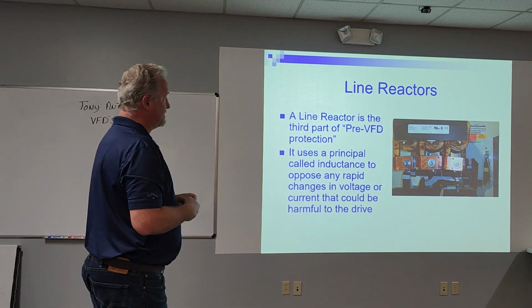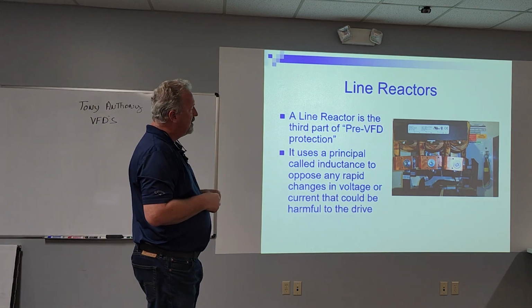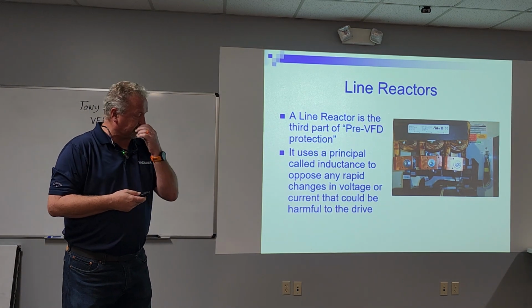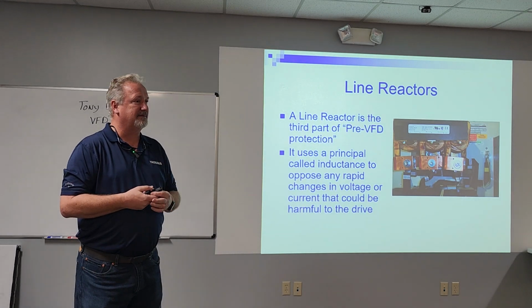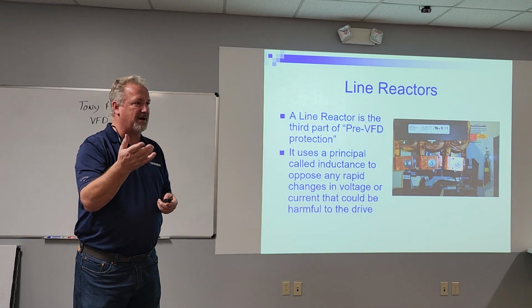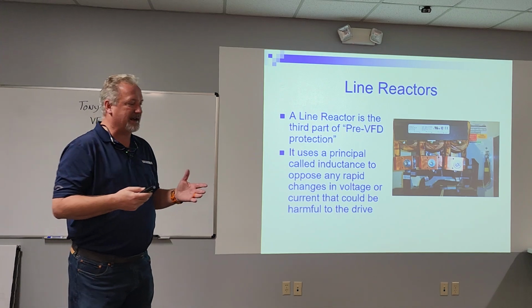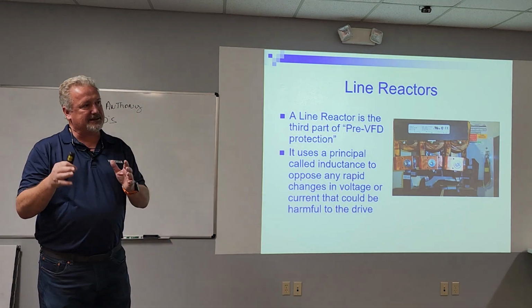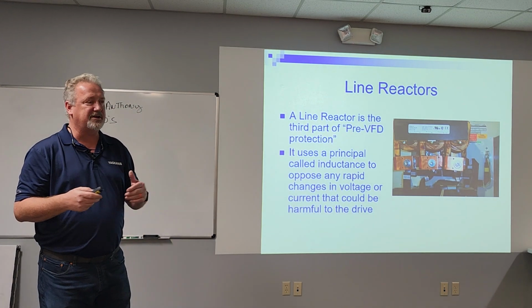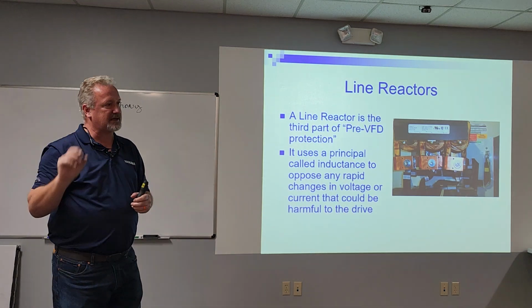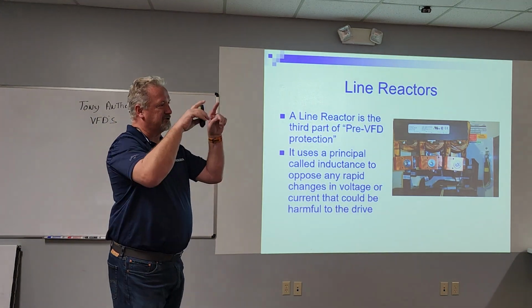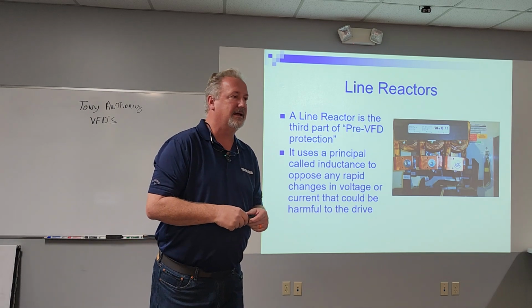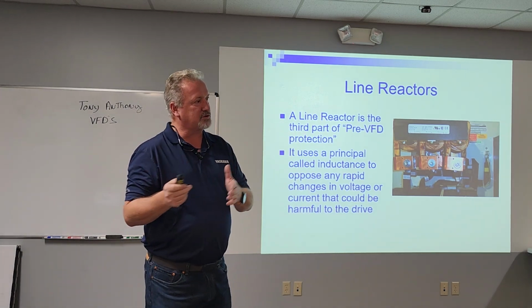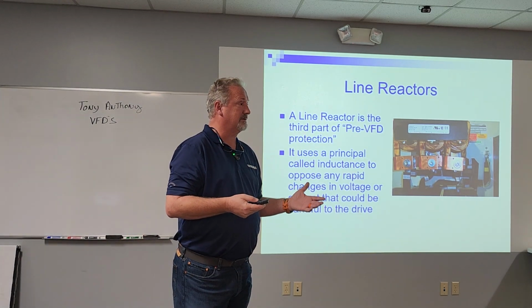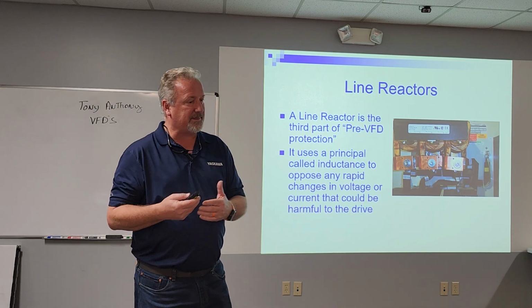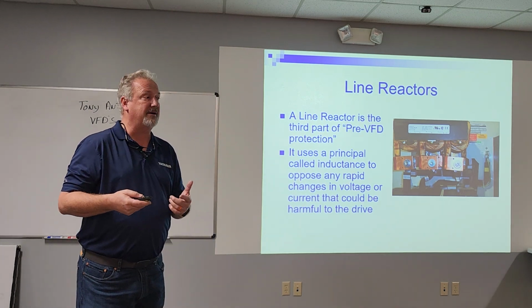One of the other more common things you'll see is what we call a line reactor. We use line reactors for a couple of things. One of the biggest is harmonics, which I briefly mentioned earlier. Harmonics are, when we're taking AC and making DC, and we'll cover this in a minute, we don't use the full sine wave. We're only using the peaks of it. So we're distorting the sine wave that feeds the drive. That distortion is called harmonic distortion. And a drive will distort a sine wave 80%.